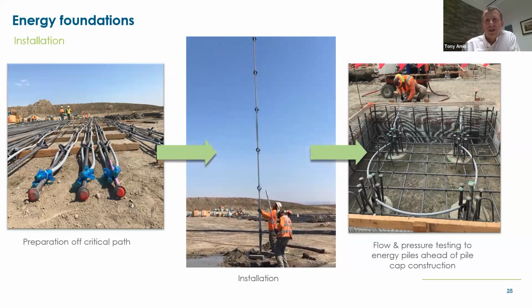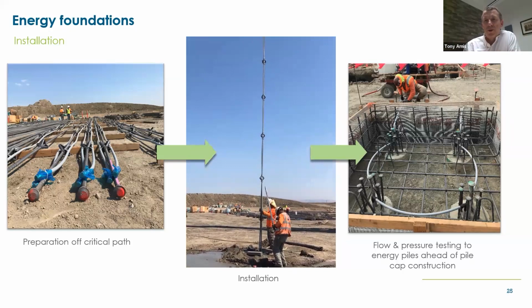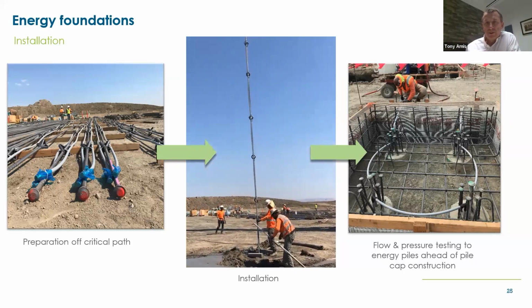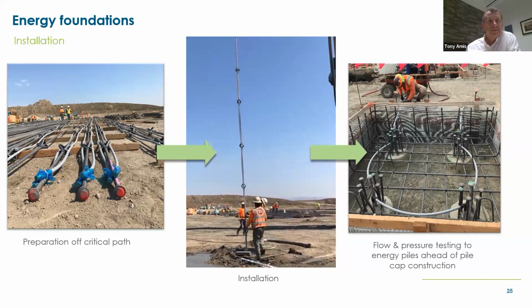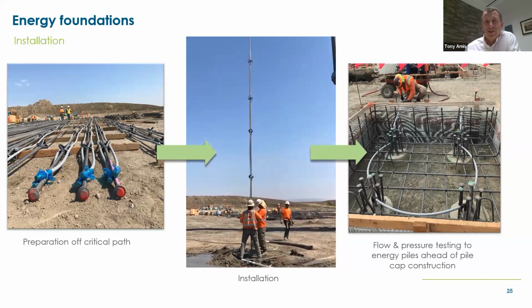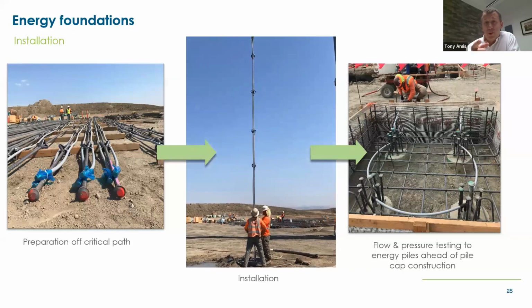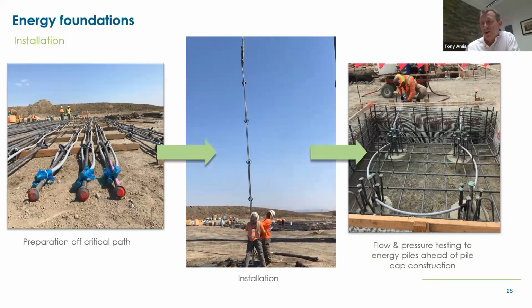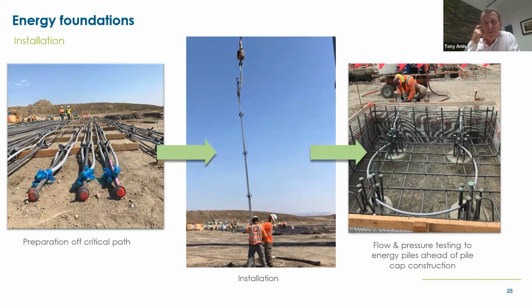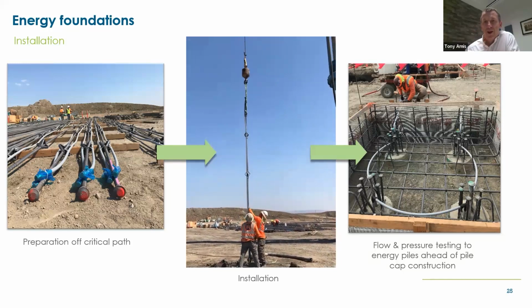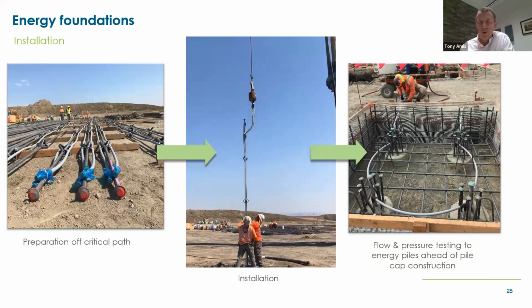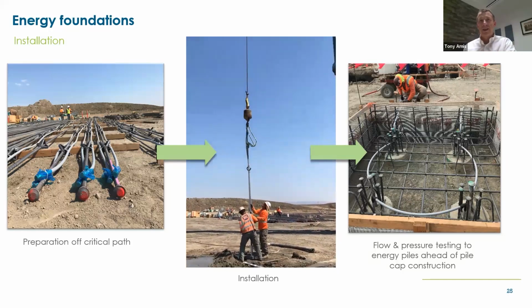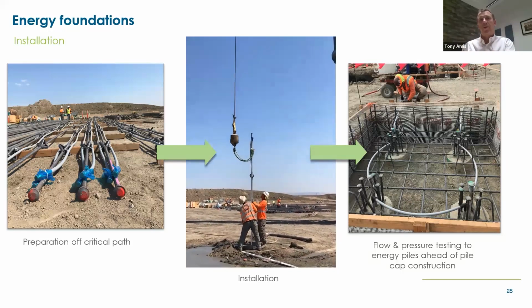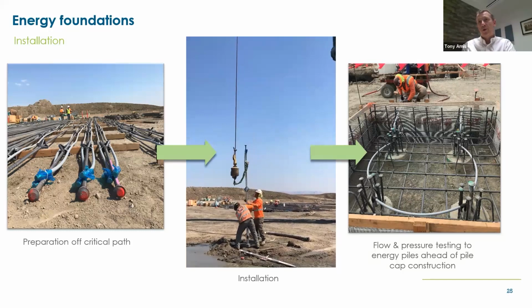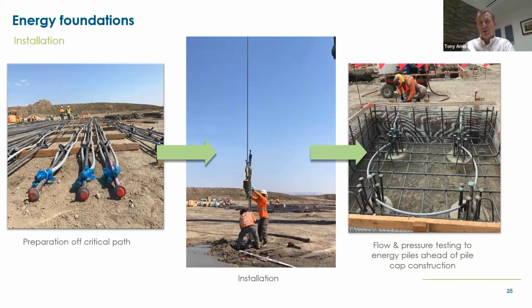So interestingly, this is 120 foot, and not wanting to give away the secret sauce from Malcolm, but these guys were drilling over 25 piles a day. If we were to drill this site with geothermal boreholes instead, in most cases they'd have drilled 500 feet of borehole in a day, and that would have been it - pretty much equivalent to maybe 4 of those energy foundations being installed.